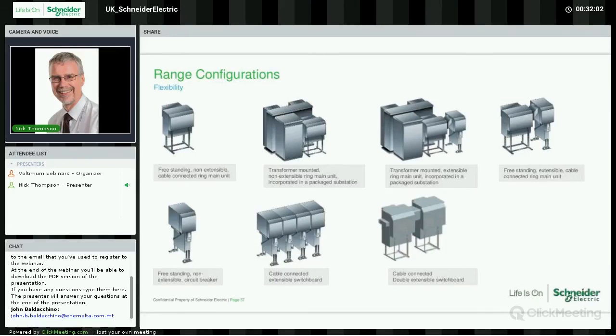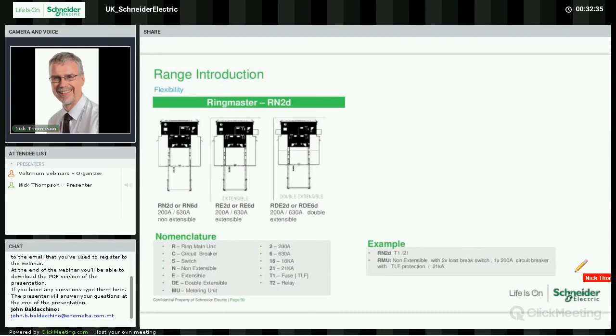Leading on to a unit which is an extensible RN2D or RE2D. This is a double extensible where you could couple two Ringmaster RN2Ds together side by side, and then we've got the top entry, either on the ring switches or the circuit breaker or both. That is for where the cables would be coming down from the ceiling, typically a basement substation. Under that application, that would only be on an indoor installation.